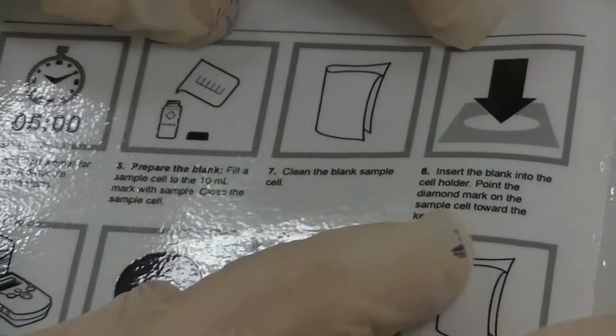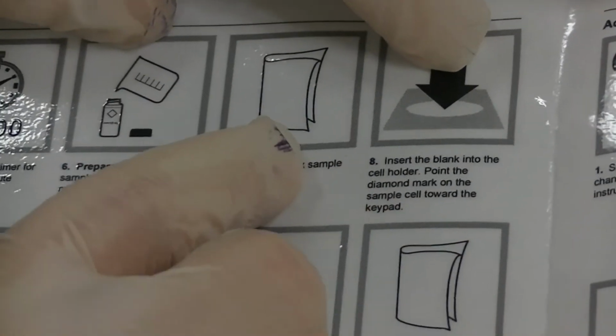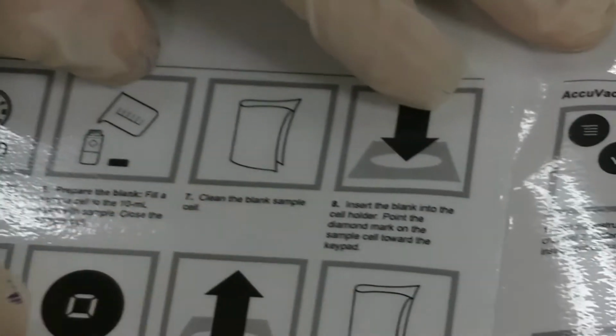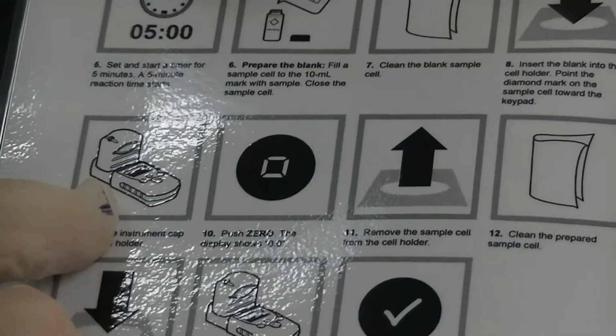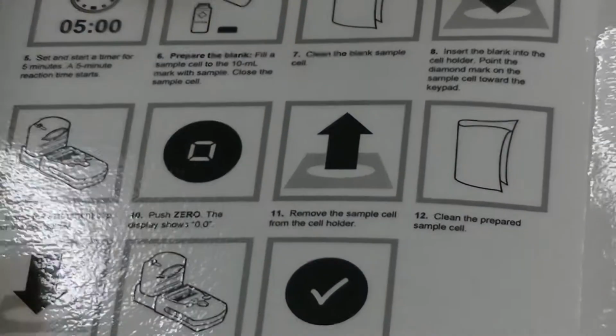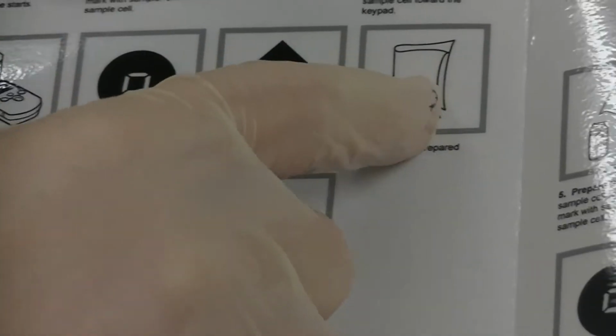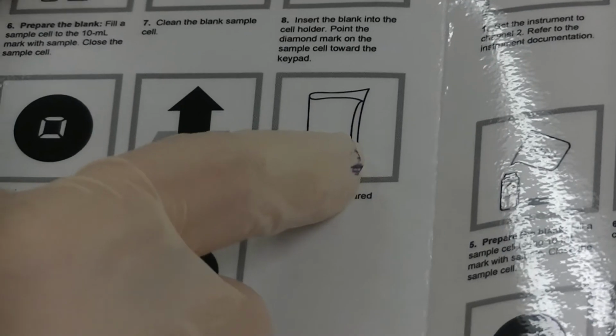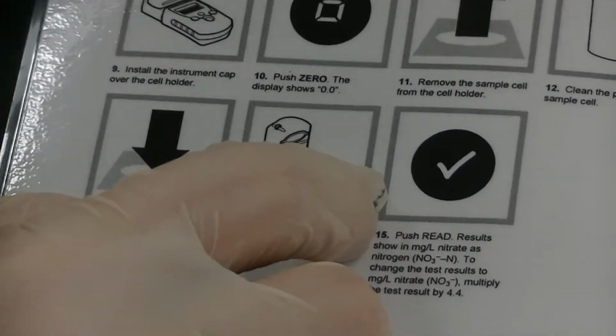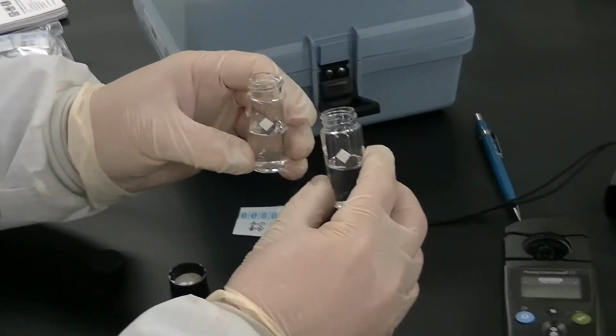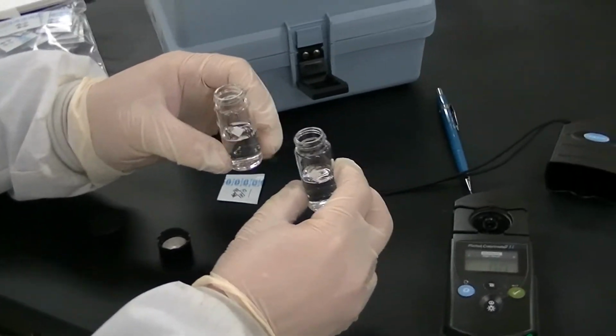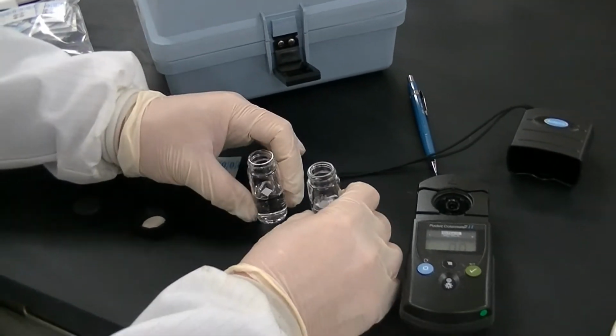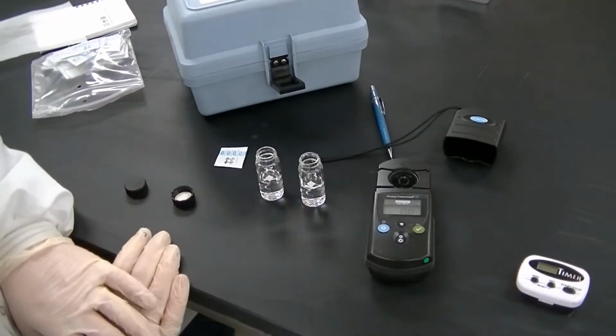So when we do the reading, we wipe down the vial and then simply insert it into the colorimeter. And for the blank, there's a blank button. I'll show you that. And then when that's zeroed, we take the sample after 5 minutes and do the same thing. Okay, so I'll show you here. I've got 2 vials full of our sample. Our sample today is the water from our lab, the potable water, drinking water. And we're going to run the nitrate on it.